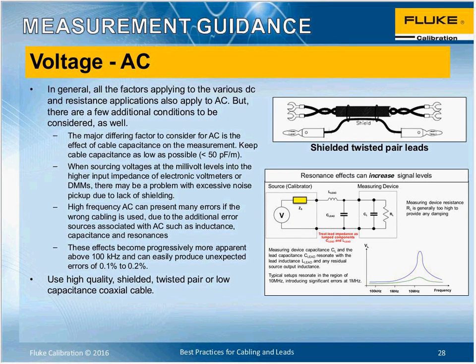AC voltage. We're going to run out of time here, and I apologize, so I'll go through this pretty quickly. After the webinar, if you have any further questions, please feel free to reach out. But voltage AC, the big factor to consider is the cable capacitance. You want to keep the cable capacitance as low as possible, recommended below 50 picofarads per meter. Source voltage at the millivolt levels into the higher input impedance of electronic voltmeters, there may be a problem with excessive noise, and this is due to the lack of shielding. So shielding is very important on AC measurements.